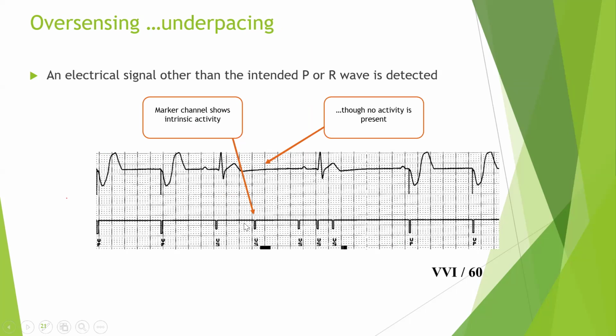Here, for example, let us go complex by complex. The first complex, you can see spike, you can see QRS, and in the bottom line, you see clearly it is labeled with V-pace. So the device is pacing appropriately. Here, there is another spike followed by a QRS, and the device is capable of seeing that, so it is V-pacing. There is a QRS, the device senses that QRS, and as a result, did not pace. But after that you see in the surface ECG, there is a T wave, not followed by anything, no QRS after that. But if you see the line below, it's showing V-sense, meaning that there is ventricular sensing activity. So the device is saying that I can see an R wave, or I can see the ventricle is depolarized. So as a result, it withholds pacing.